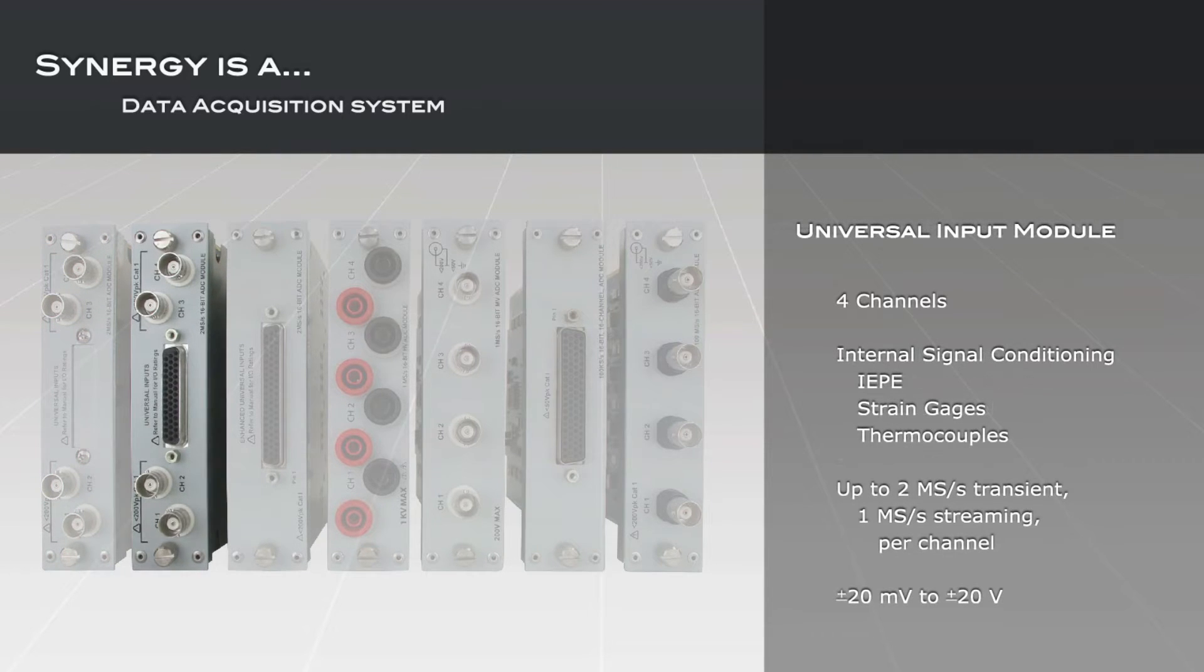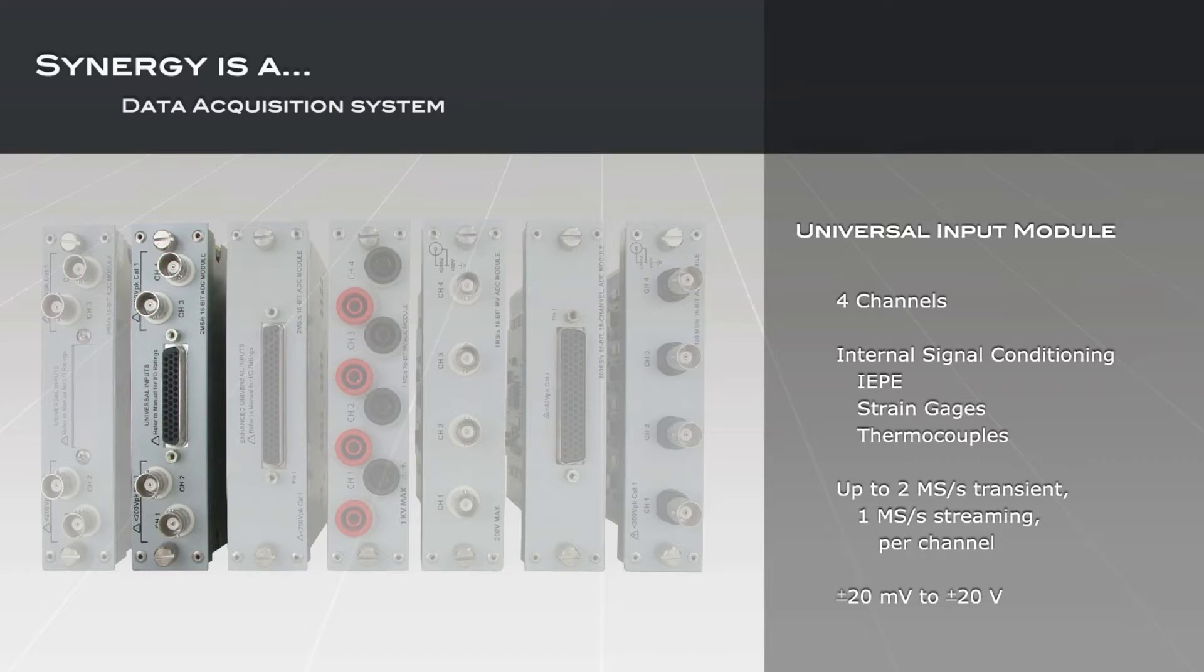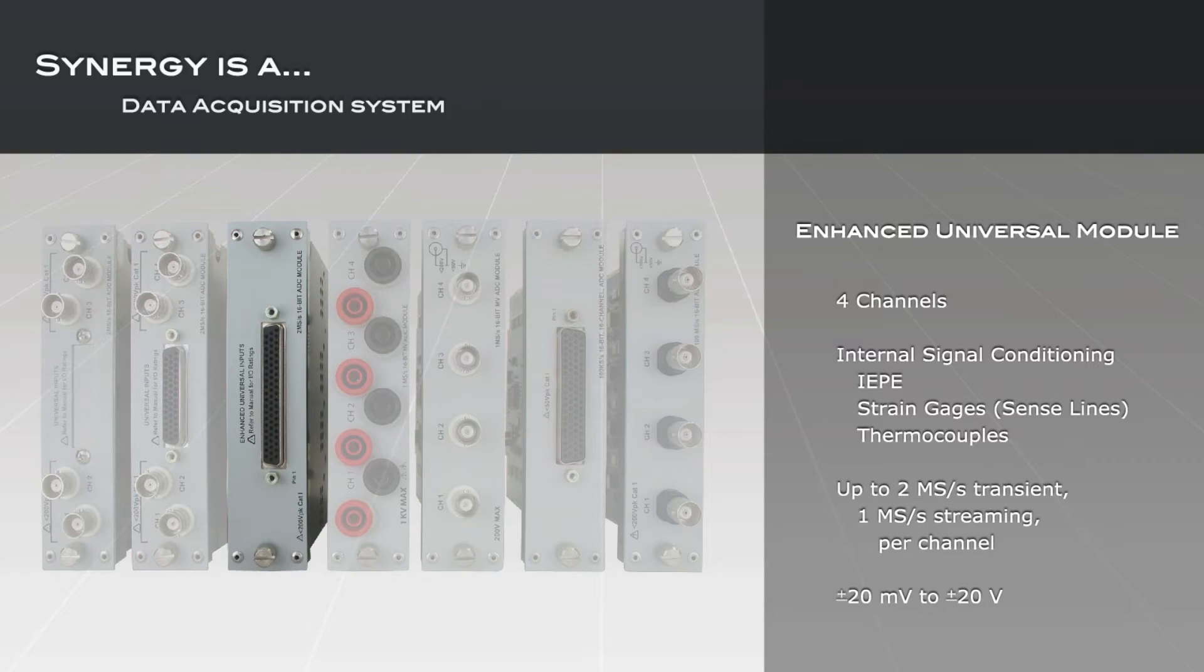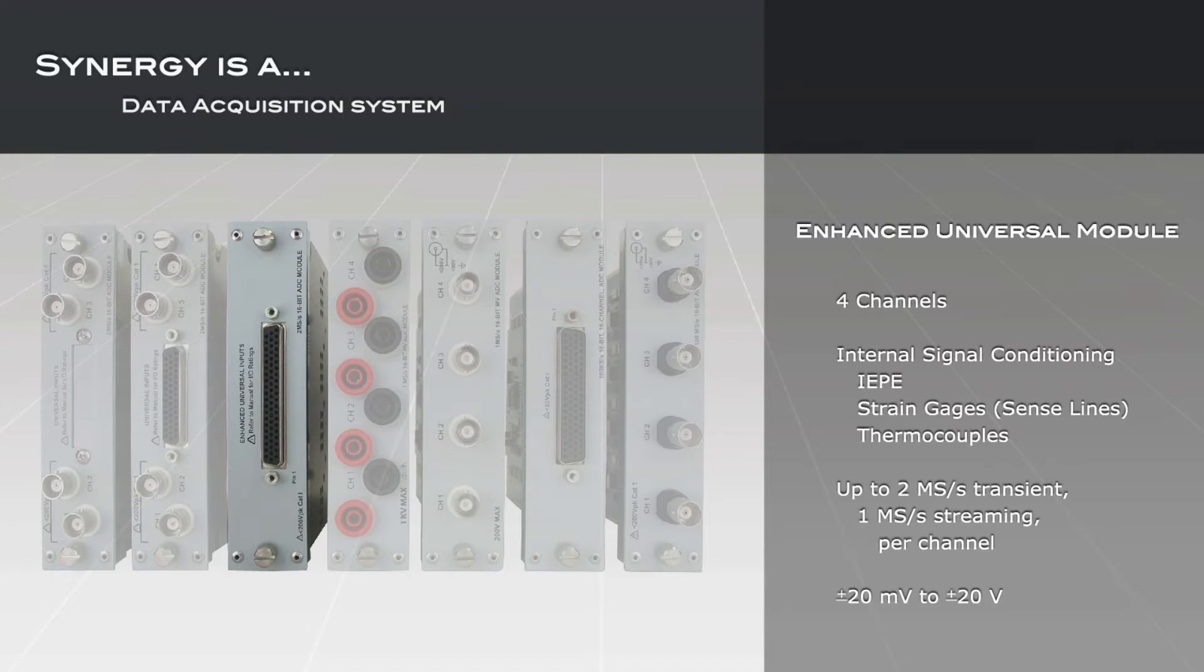Expanding on the basic module, the universal input module provides signal conditioning for virtually all sensor types and can be software-configured and reconfigured on a channel-by-channel basis to accommodate changing test requirements. The enhanced universal input module allows individual channel excitation, remote sense lines, additional radio frequency filtering, and input protection. The enhanced UI is intended for applications requiring long sensor leads.